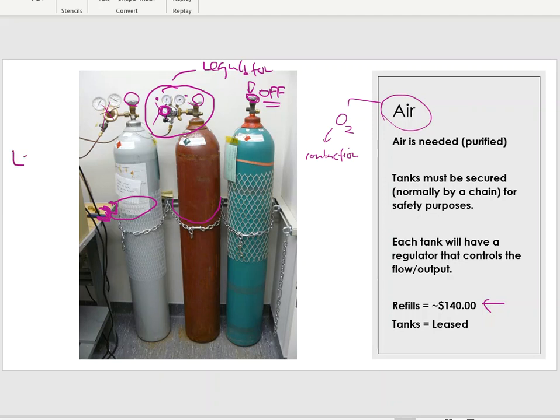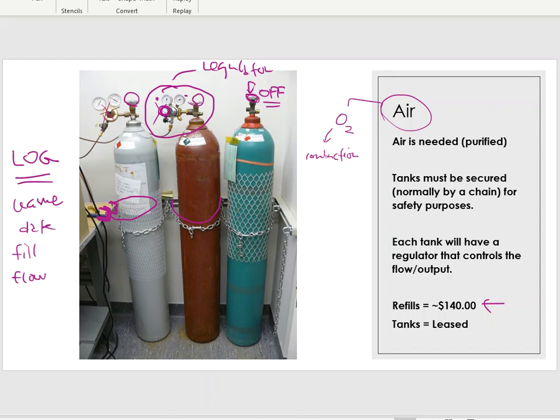One more thing to leave you with: it's not uncommon for labs to keep a log book on their tanks. You would write your name, the date you used the machine, the current fill level, and the flow rate. This lets the laboratory track who's using the machine, catch any leaks or anomalies, and monitor gas levels so a replacement can be ordered before the tank runs out.